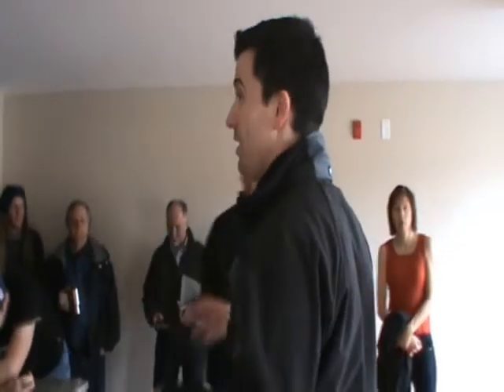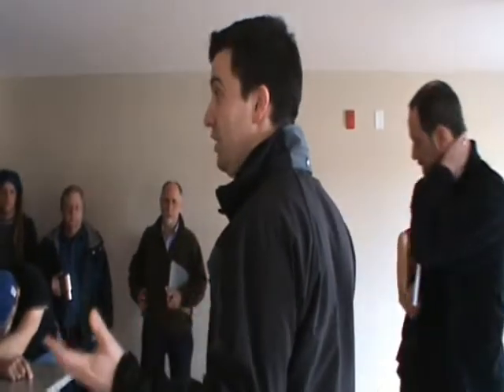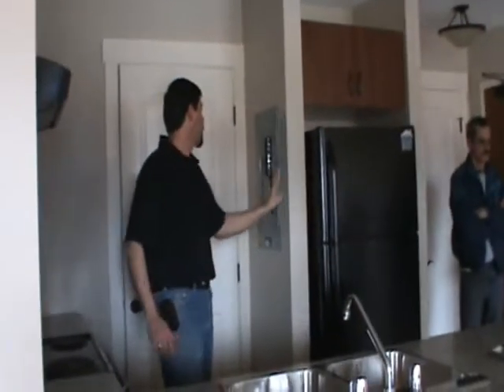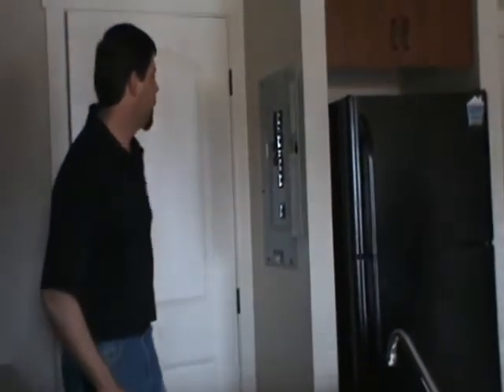Okay, this is the 2-bedroom residential suite. All of the suites are 100 amp service. There's no change in size. In this suite, the panel is there. Every suite has its own panel. All the loads within that suite are fed out of its panel.